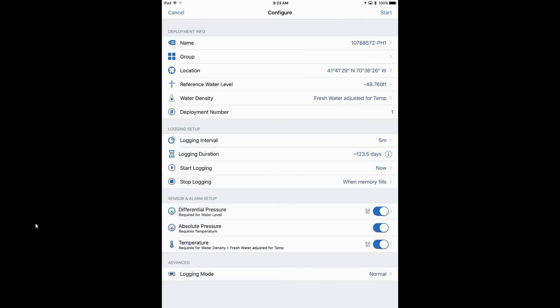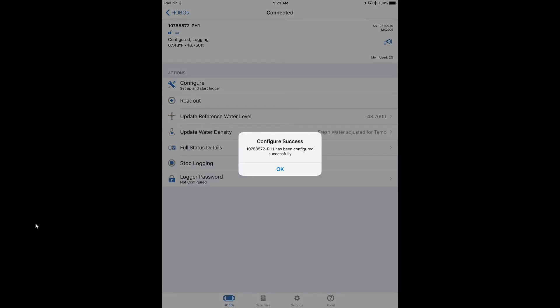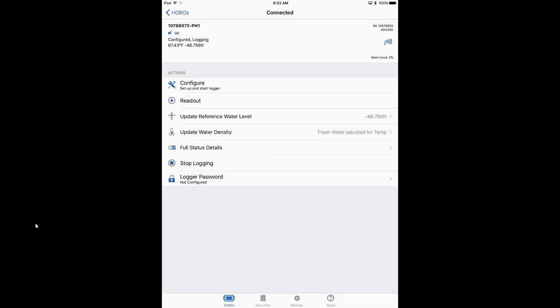If we click up in the upper right-hand corner and tap on Start, it will say 'Configuring logger' and it will begin logging. It has now been configured successfully, and in the upper left-hand corner it shows it's configured and logging — we are ready to begin our deployment.